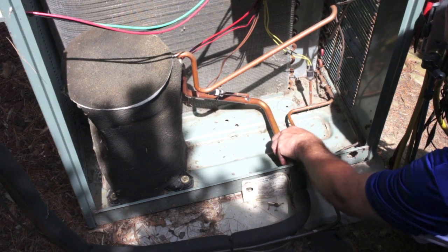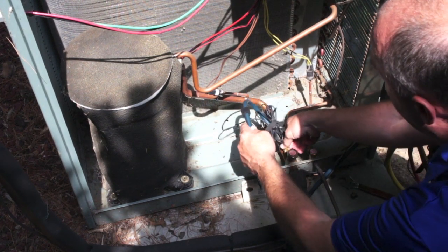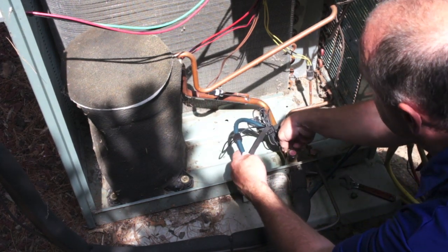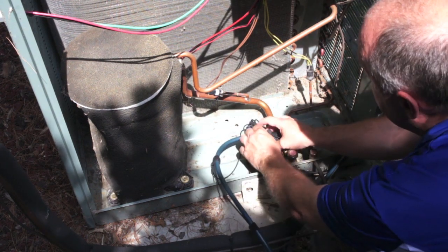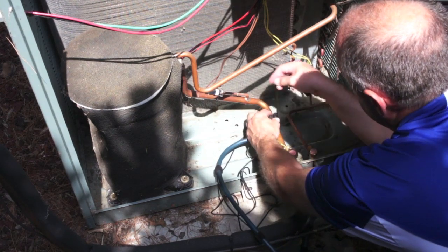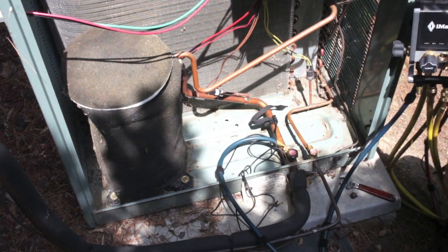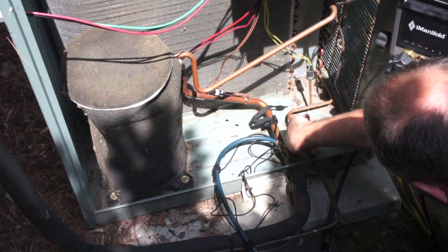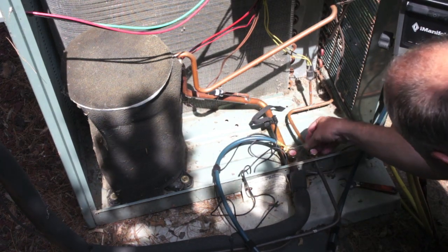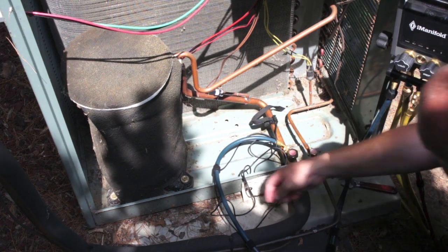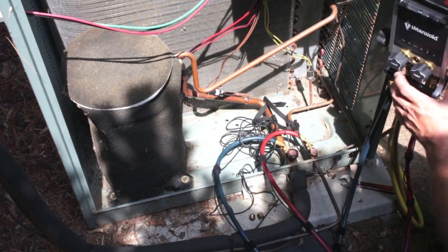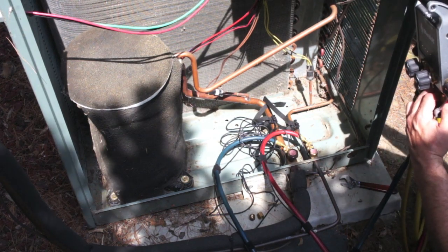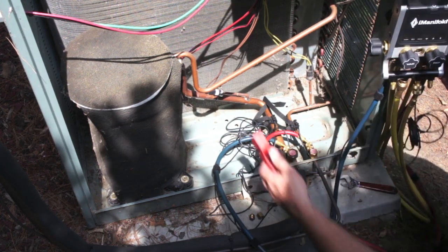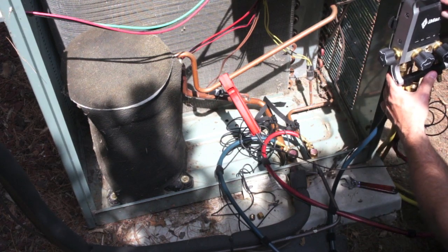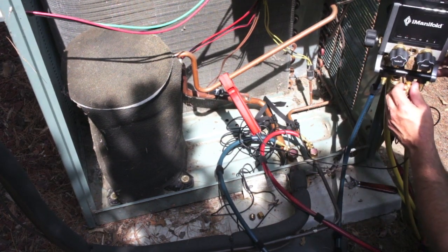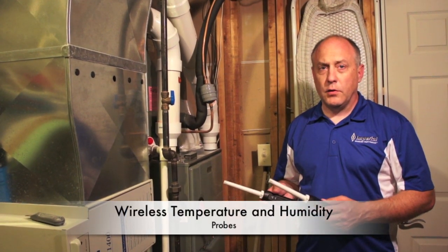So we're going to go ahead and hook up the suction line and liquid line. I wanted to go through the whole process this time just so you can get an idea how much time things take. And you can see here, right now I have my probe right where I need it. Strap it around and it's on. Same thing with the high side fitting. Clamp this onto the discharge line. Turn the iManifold on. We have everything connected.